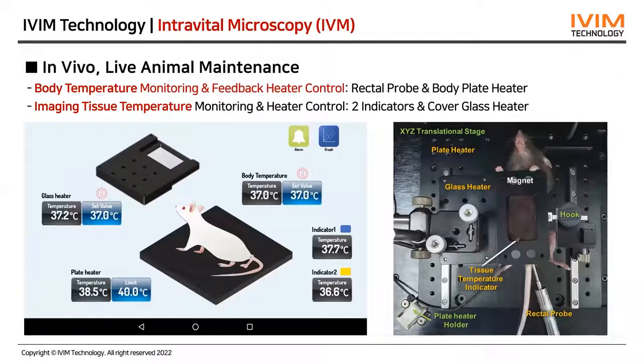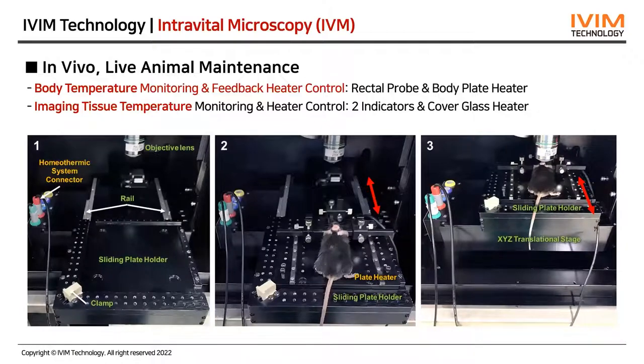We also provide various additional accessories for maintaining the healthy condition of a live mouse model during in vivo experiments. These include a rectal probe sensor for mouse body core temperature with a feedback heating plate system, and a glass heater for local tissue temperature maintenance of the imaging organ. If you need to move an organ slightly out of the body to image, this tissue temperature heater with an integrated cover slip maintains local tissue temperature. The translational stage is used for mounting the mouse model, with all accessories connected via a connector on the left.